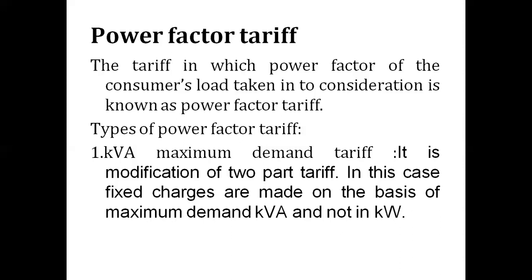A low power factor increases the rating of station equipment and also increases line losses. That is why we design a Power Factor Tariff — to account for the impact of low power factor on station equipment rating and line losses.